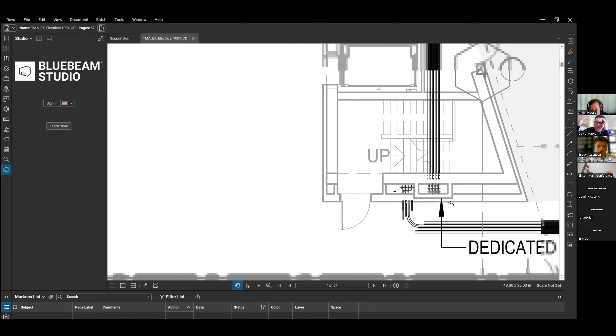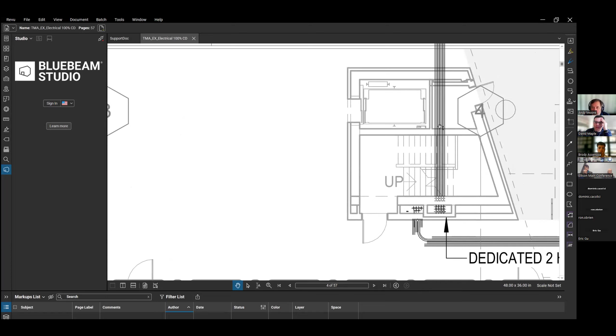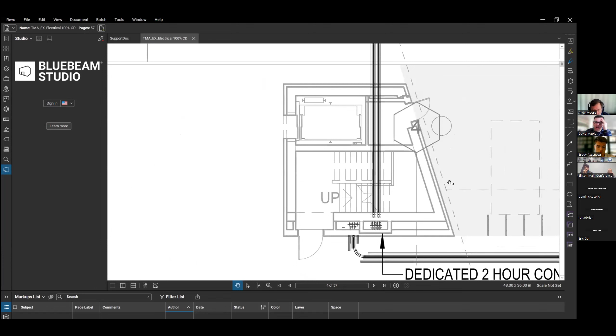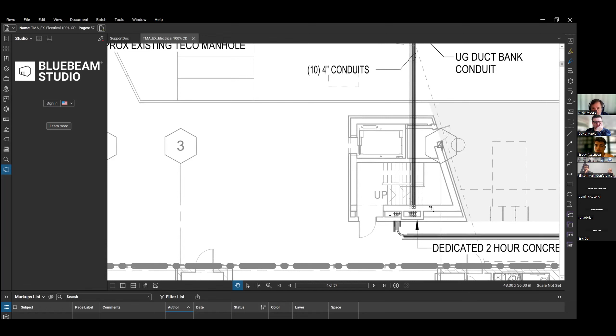To Ron's point, we know how much duct banks cost and the premium put on them. So what we tried to do was locate these central to the east core of the new project, the staircase and elevator, and run it up along the south side, so they don't overlap each other but can run straight up through the building uninterrupted with no offsets. It goes below the staircase, but to the east of the elevator. There's a bit of coordination with the conduits and their elevation, but we think it's the cleanest way to get it into the building without a lot of sweeps. This is a straight shot, a dedicated chase right up to the second level to the main electrical room, with the main switchboard.